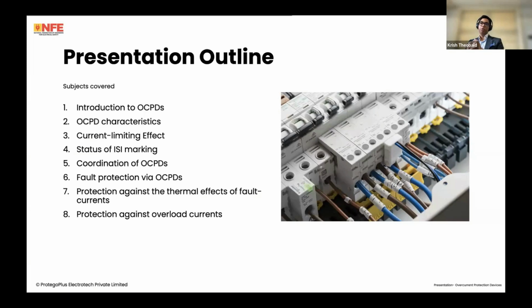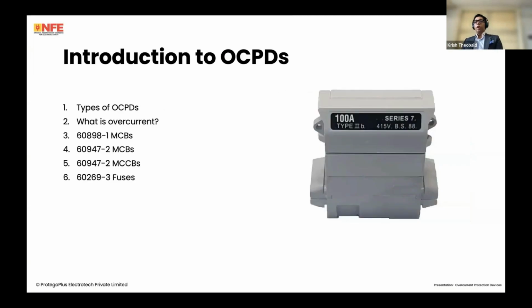Fault protection is in failure of these situations, how you achieve automatic disconnection of supply, and how this ties in with protective earthing and protective equipotential bonding. We also delve slightly into protection against thermal effects of fault currents and protection against overload currents.